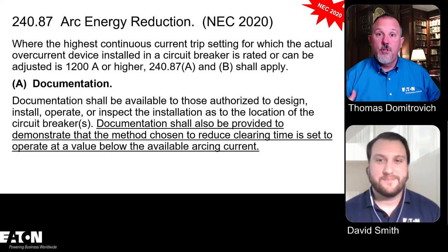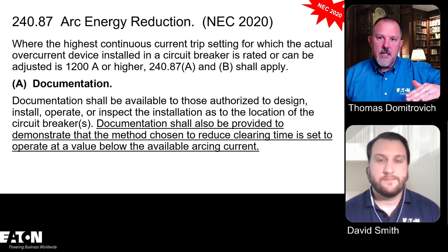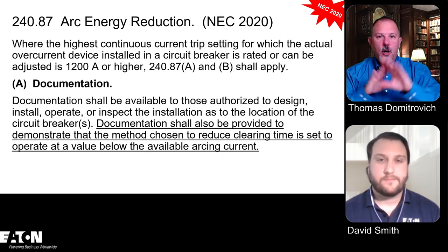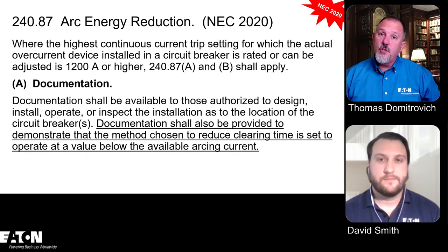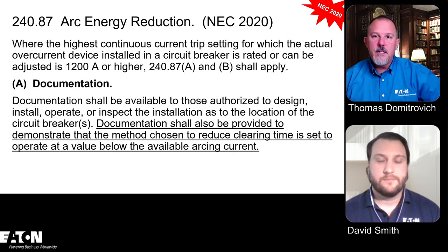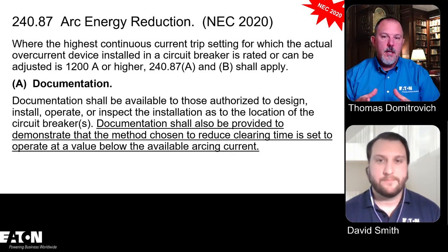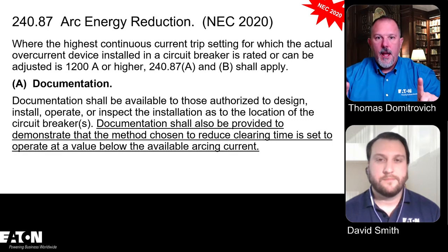And typically as an engineer, what I'll do, and you said it earlier about motor contribution, is turn all of your motors on and figure all of your impedances at their lowest values from transformers and whatnot. Because remember, on a transformer, you have to do plus or minus 10%, right? Sure. So you would do minus 10% on all of those, get the highest fault current, and then turn all those motors off, model the system with all the motors off, with the highest impedances on anything that has a range of impedances like transformers. And you get those two bolted fault current values. And then you calculate two values of arcing current for each of those and establish the clearing times, whichever gives you the highest incident energy. That's what you label with, right?